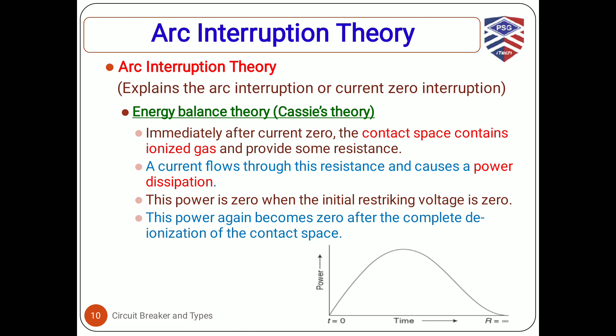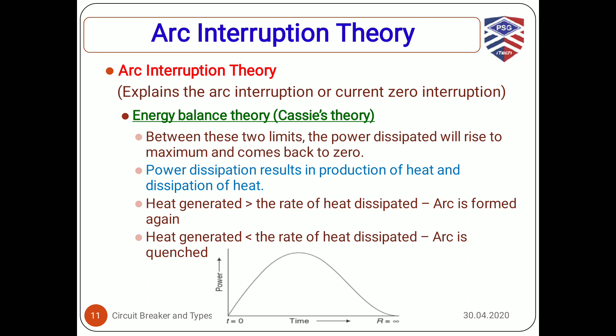So the energy balance theory explains the arc interruption, how the arc can be interrupted, based on the heat generation and the heat dissipation. It is summarizing that it is a race between the heat dissipation and the heat generation. So if the heat generation is more than the rate of heat dissipation, the arc cannot be quenched, or will be formed again, because more and more heat is generated and you are not able to interrupt or quench the arc between the circuit breaker contacts. Otherwise, if the heat generation is less than the rate of heat dissipation, the arc will be easily quenched. So these are the two arc quenching or arc interruption theories, which explain how arcs can be interrupted.